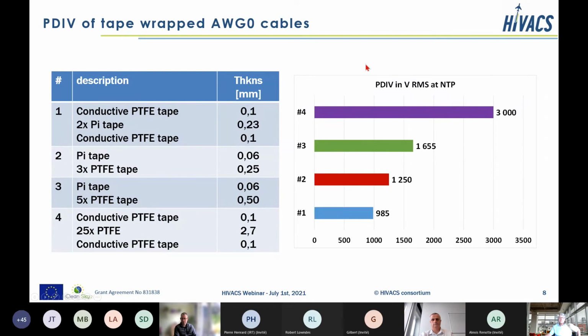Here on the right hand, we see the obtained PDIV results, and surprisingly, the PDIV of the screened cables is quite low, much lower than what we have expected. So, for example, for the first one with the polyimide tape as insulation, we only have 1 kV of PDIV, and for the fourth cable with the thick PTFE insulation, we only have 3 kV. And for the two unscreened cables, again, we see the increase of the PDIV with insulation thickness. And again, we see that it is not a linear relation.